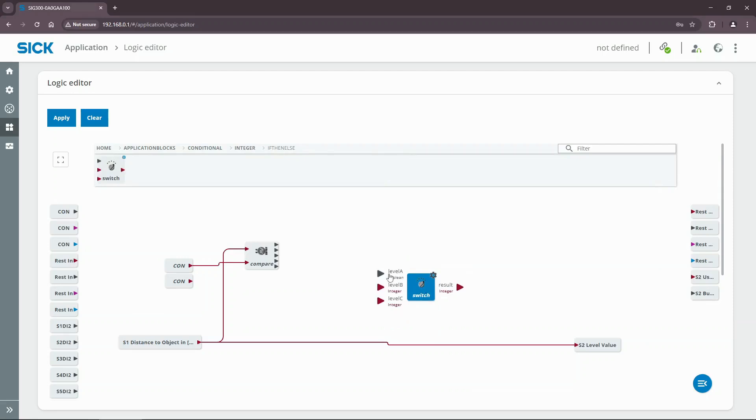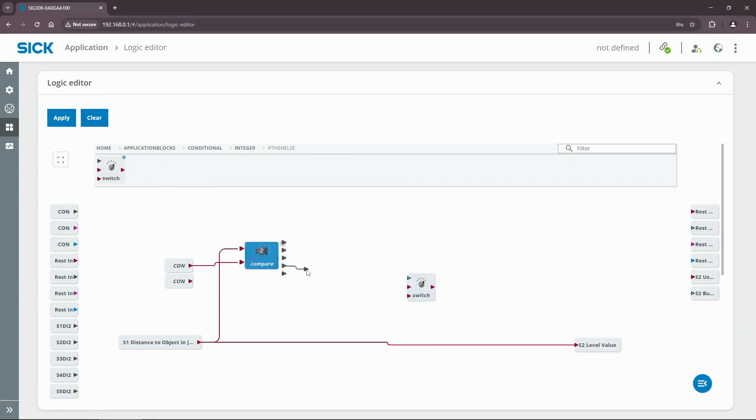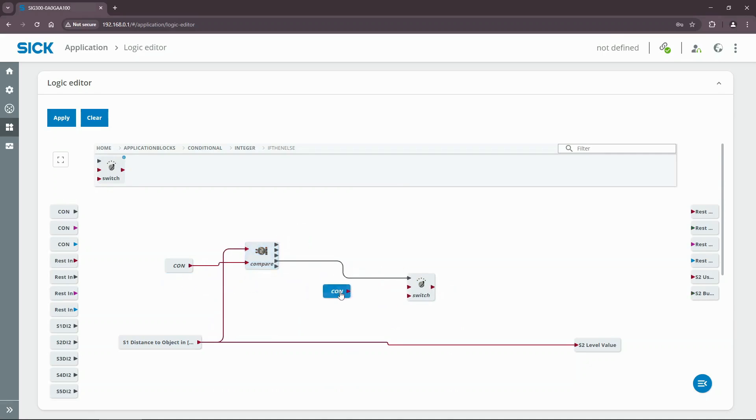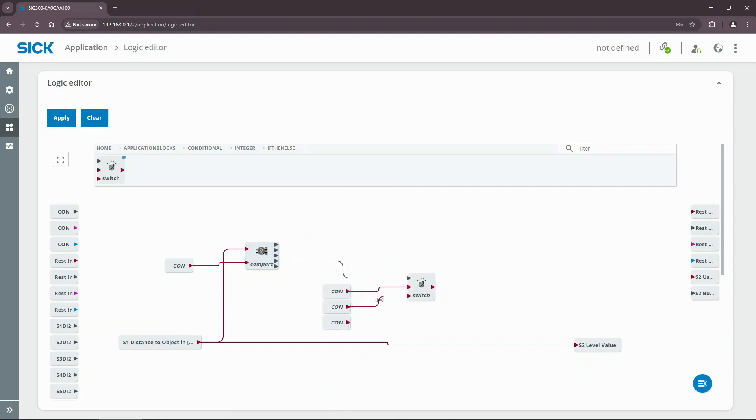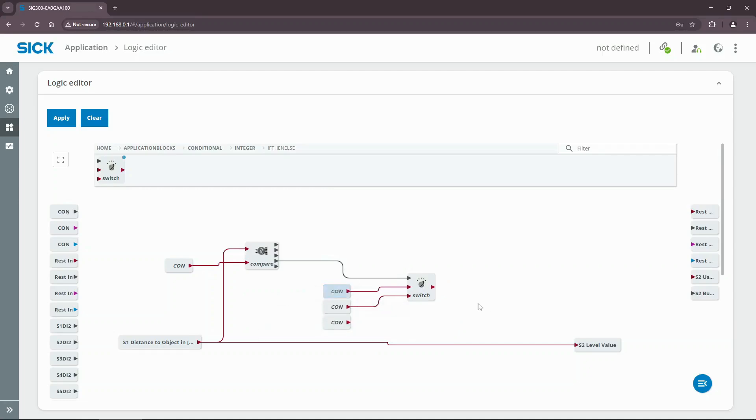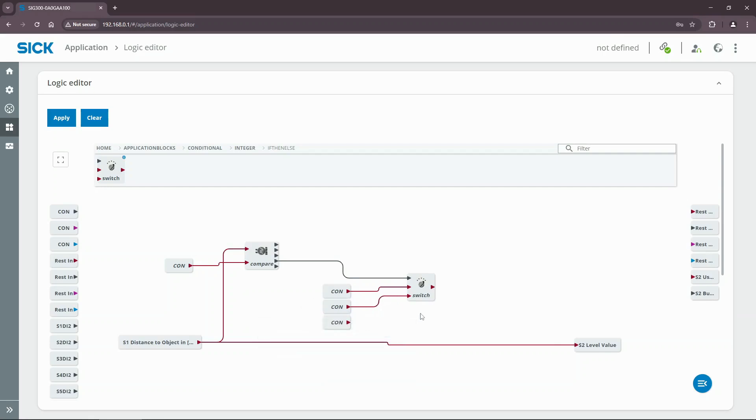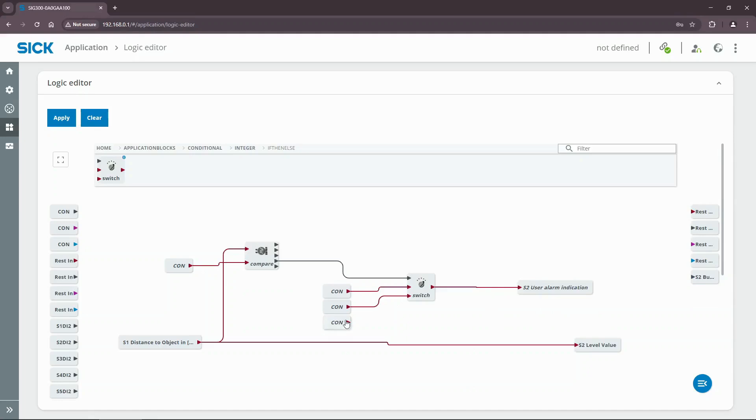Connect the GEQ output of the comparator to the level A input of the switch. Then connect two integer constants to the switch inputs level B and C. Set the constants value to 1 and 0 accordingly. Connect the output of the switch to the S2 user alarm indication block. Apply the logic.